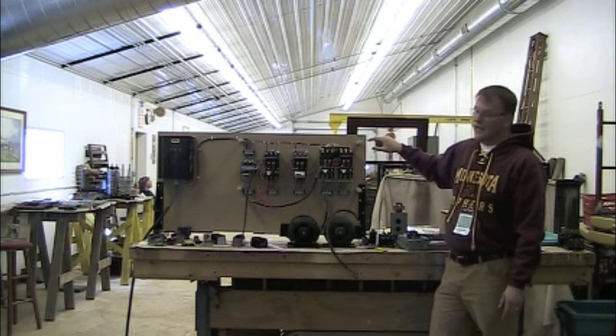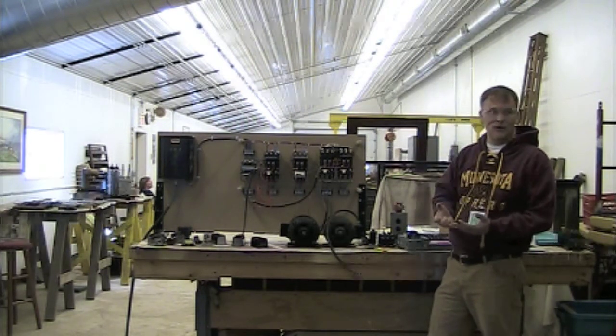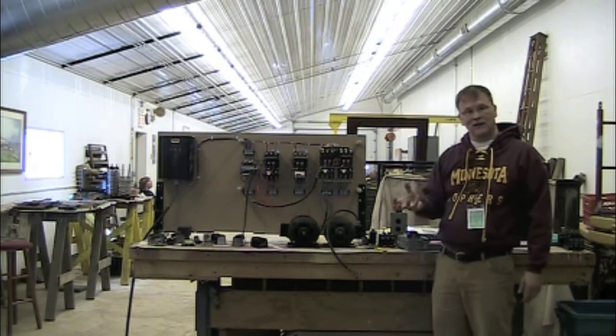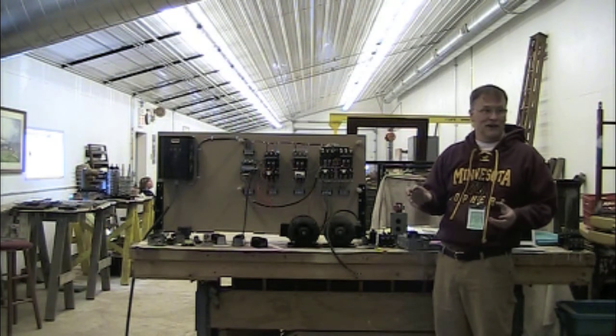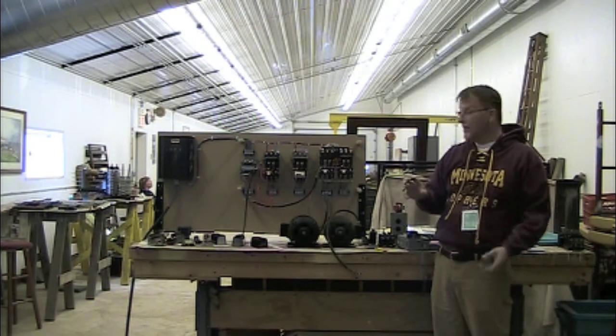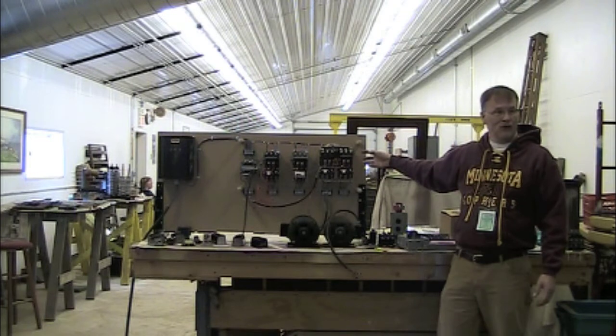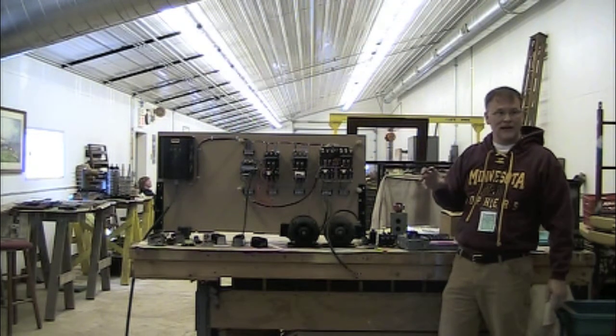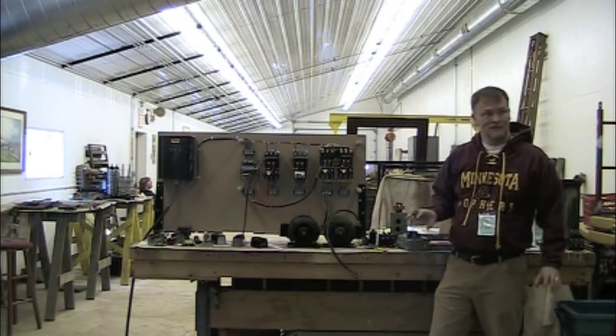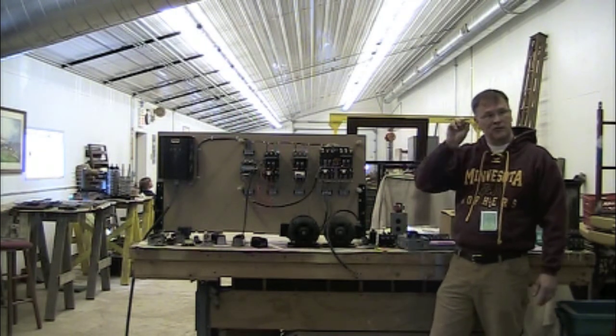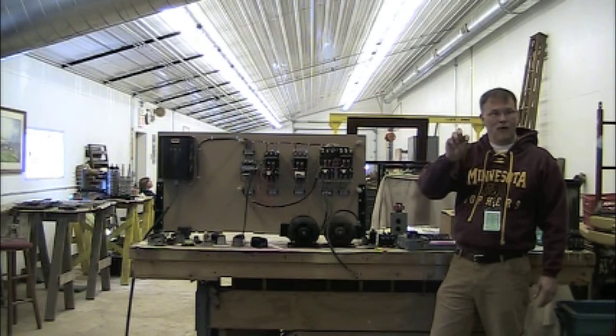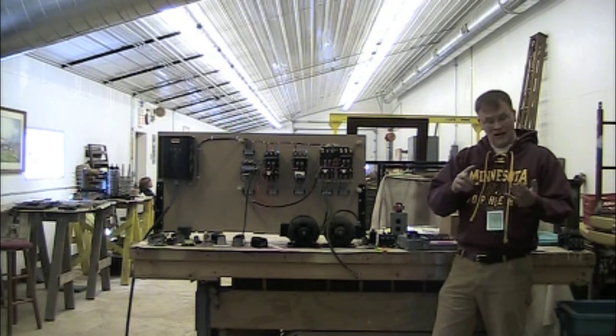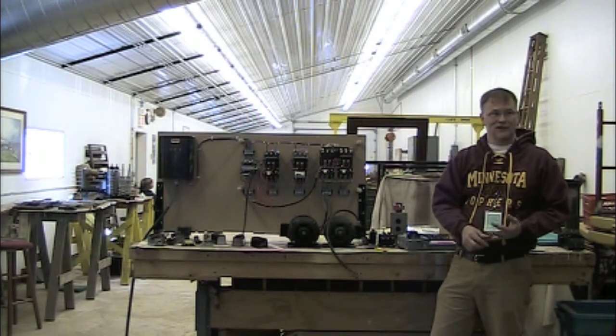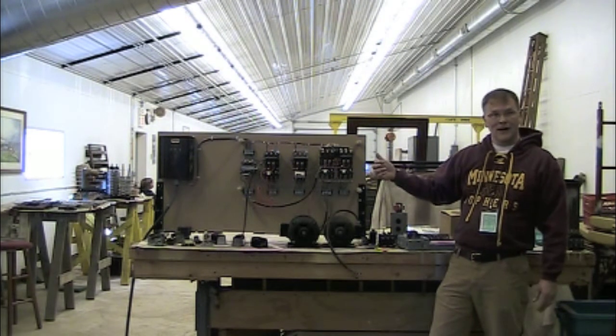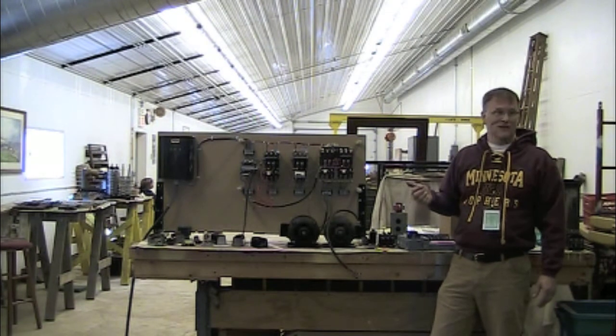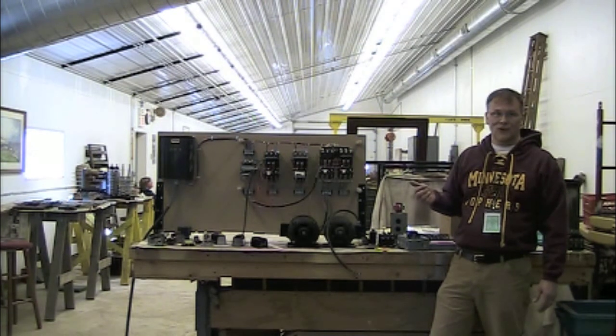So if you need to control a consequent pole motor, now it's much more complicated, because you're actually rearranging the winding configurations in the logic of what the thing is doing. So it actually requires extra poles on the side of here to be able to make those other connections, and a lot of other things in the control circuit. So there are specific Bulletin 521s for the different types of multi-speed motors, whether they're constant horsepower, consequent pole, constant torque, or separate winding. So if you really need one of those and looking for them, it can be hard to find, especially for those more exotic types.